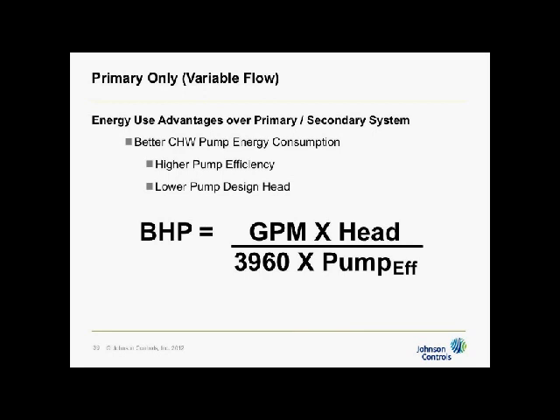VPF also has the advantage that it improves the energy use over primary-secondary. The first reason is that we have better chill water pump energy consumption. One reason is because we have higher pump efficiency. This is because we're combining the primary and the secondary together and having a higher head with the pumps. Typically going to higher heads moves you into a more efficient region of most pump curves. And usually the pump curves for a primary circuit being somewhere around 40 feet will put you in 1100 RPM motors if, again, you're on 60 hertz. It'd be around 1150 RPM, and that usually is less than 80% efficient. When we go to one pump up at 140 feet, then we'll be up there in the 85% efficient range. We also have better energy from it because we have lower pump design head.